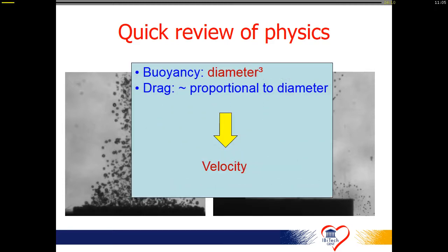So we have actually two main forces. We have the buoyancy, which is mainly depending on diameter, meaning that when you have an arterial screen filter, what it will remove very well are big bubbles, around 500 micrometer. But once they become smaller, they are actually captured inside the screen, and they probably will remain there or when they are diffused, or they will pass the screen.